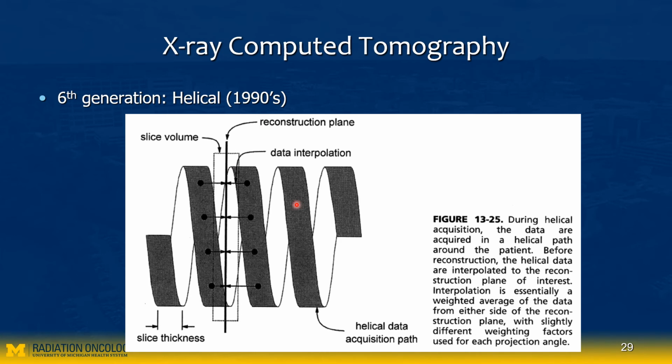So in this example, pitch is obviously bigger than 1, and when you reconstruct a slice at this Z location, it interpolates data that is before and after to recreate this actual cut. The acquisition is helical with this little bit of angle because we acquire the image while the table is moving, but you have to reconstruct this actual cut by using this neighboring information.